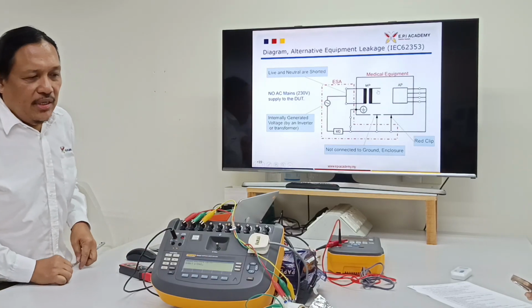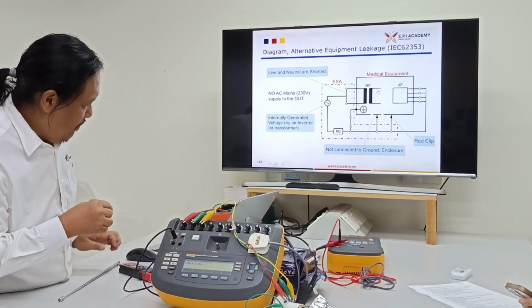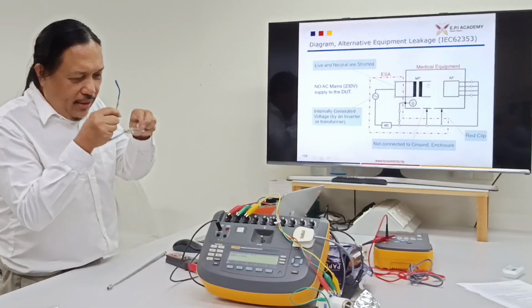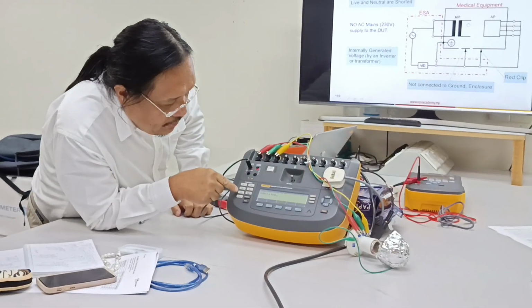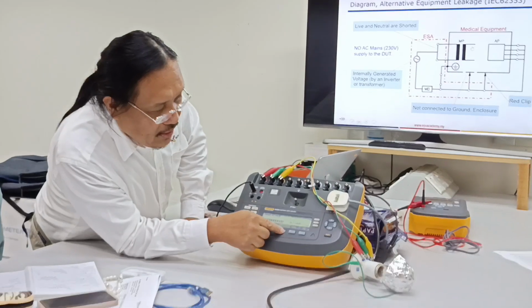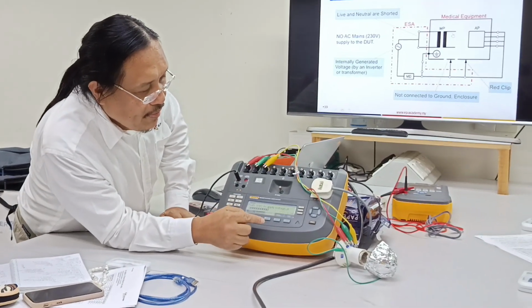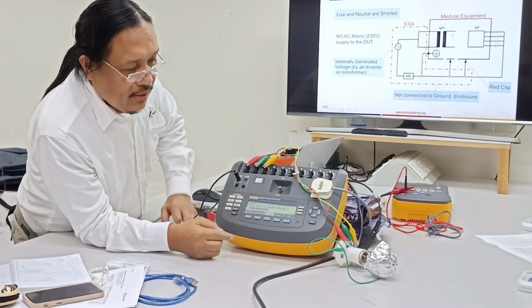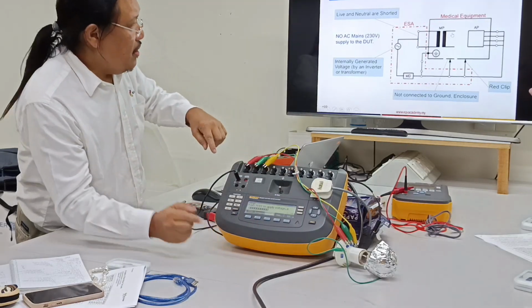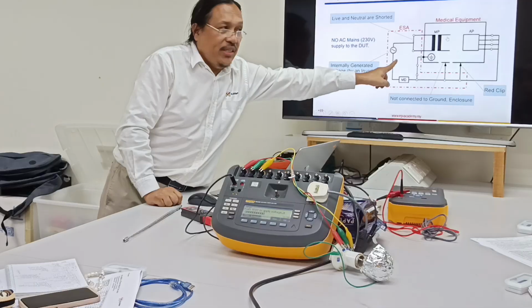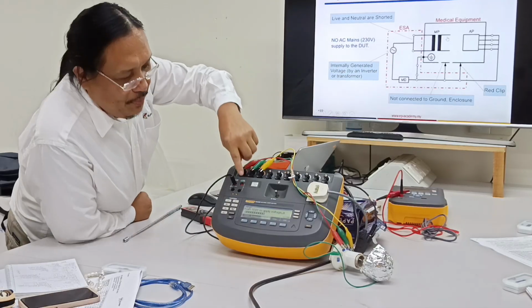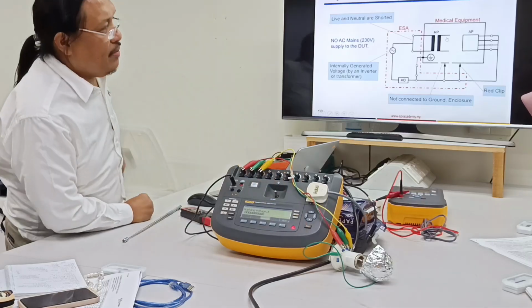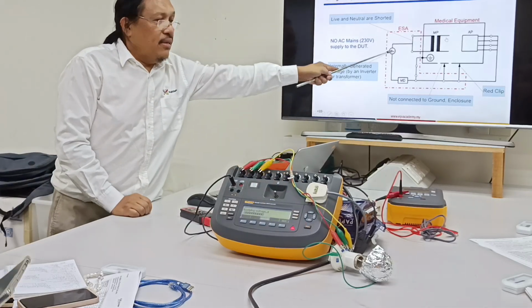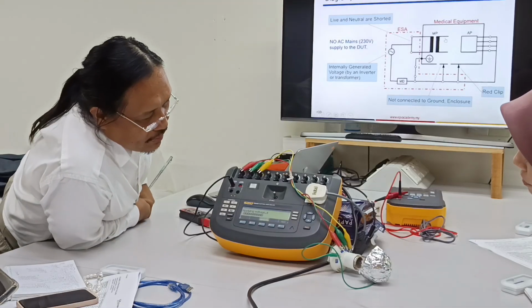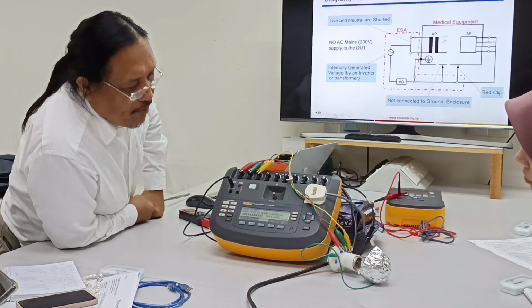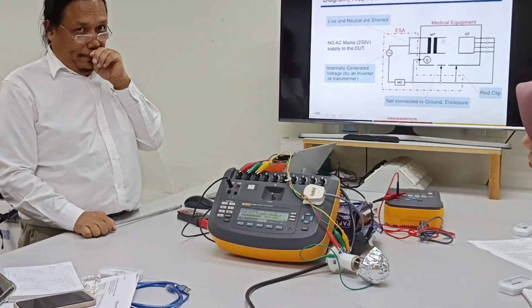So, easy to demonstrate. Just select micro A and select alternative. There's an instruction like here: press test to generate this, to turn on this one. Press test to apply the voltage. So that voltage. That's the leakage, 194.6.